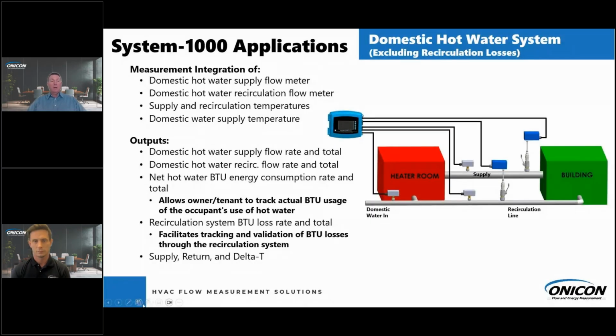So what did we do here? We took a domestic hot water supply flow meter going up into the building. We have a domestic hot water recirculation line flow meter returning to the heater room. We'll have supply and recirculation temperatures, and then we'll have a domestic water supply temperature. In this orientation, it uses both channels of the System 1000 and gives you domestic hot water supply flow rate and total. It gives you the flow rate and total of your recirculation line. And then using the energy difference between these two, you get a net hot water BTU energy consumption as a rate and total.